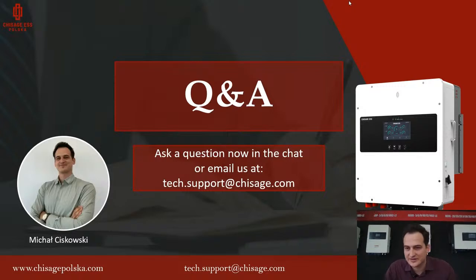the question is if we need any special automatization to change from backup to regular power. No, we don't need it. If you put something in a backup load, all this backup load will work on-grid and off-grid all the time. If you put any load to the backup load port, the inverter will take power from the grid, from the battery, from PV, and when the grid is off, the inverter will switch to off-grid and still power this load. So no need to add any other devices. The inverter will manage this by itself.